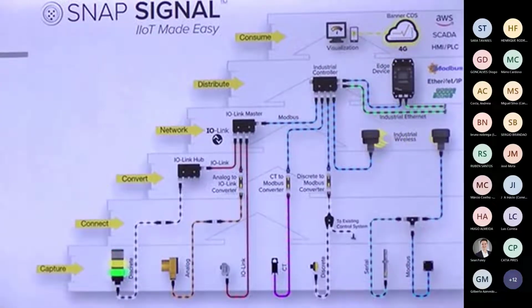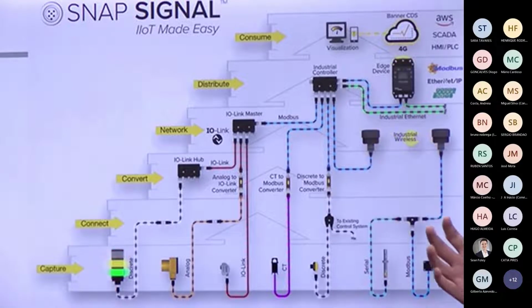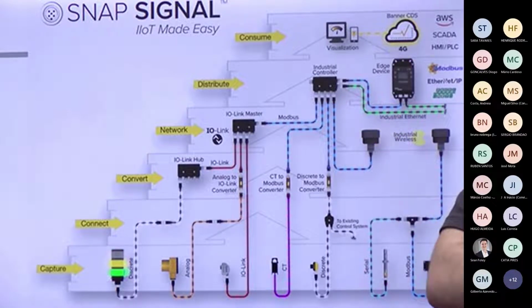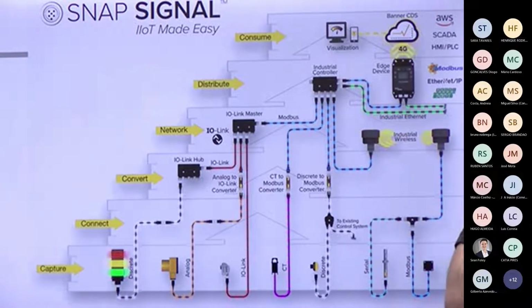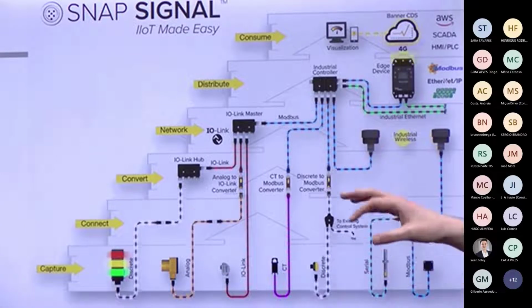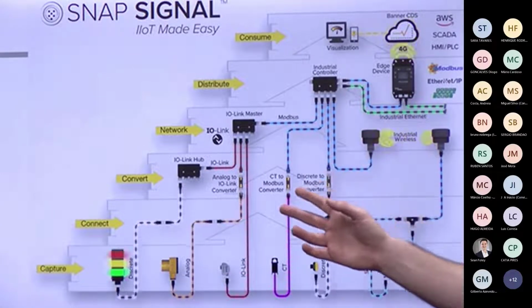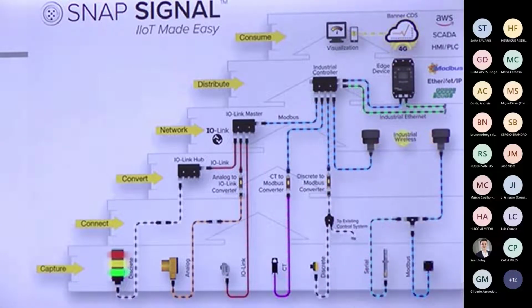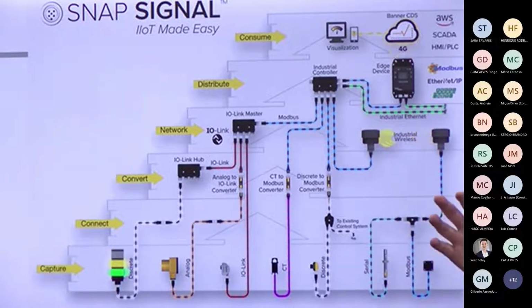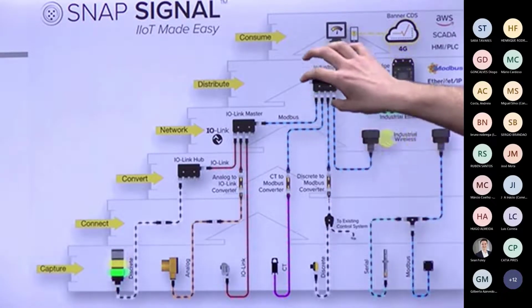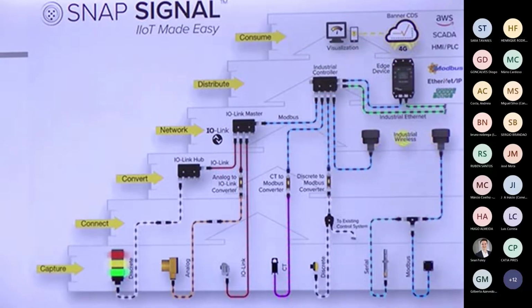With Snap Signal, what it's really all about is adding this technology over the top of your existing control system, so we're not disrupting your existing control system at all. What we're doing is taking in all these different signals, converting them over to a unified serial protocol, an RS-485 protocol, so they're all talking the same language. And we're able to take it into our DXM R90 Industrial Controller.